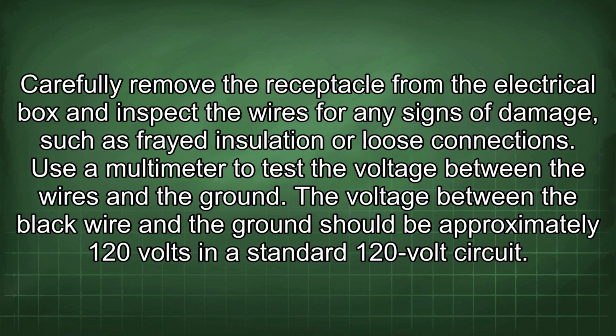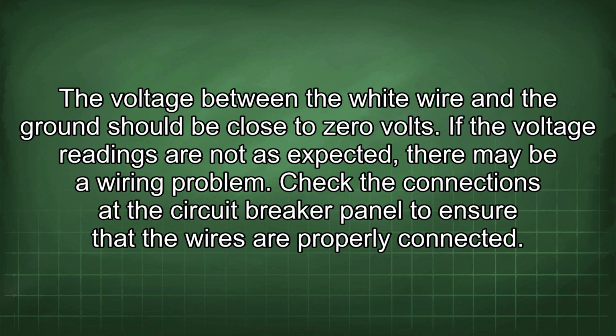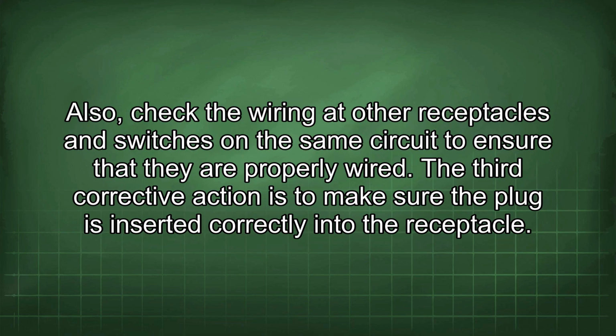The voltage between the black wire and the ground should be approximately 120 volts in a standard 120 volt circuit. The voltage between the white wire and the ground should be close to 0 volts. If the voltage readings are not as expected, there may be a wiring problem. Check the connections at the circuit breaker panel to ensure that the wires are properly connected. Also, check the wiring at other receptacles and switches on the same circuit to ensure that they are properly wired.